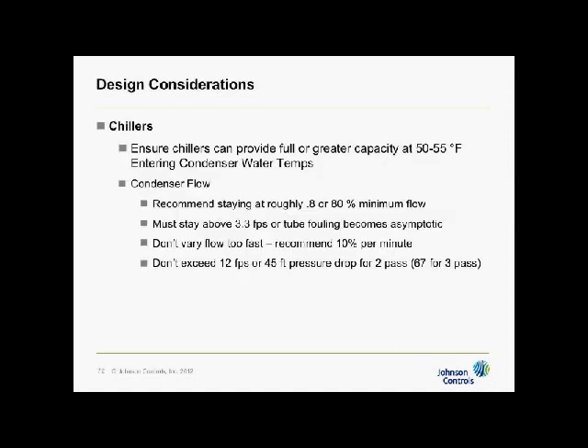On the condenser water flow, we still recommend staying roughly at 80%, go no lower than 80% of design flow minimum. And there's lots of reasons. We'll talk about that. It mainly affects the condenser. But also keep in mind, even though you're saving energy, you still are increasing your fouling along the way. So we must stay above 3.3 feet per second, or your tube fouling becomes asymptotic. And that means that at full flow, you have your standard fouling. The fouling will still increase as you reduce flow. So you don't get everything for just reduced flow.